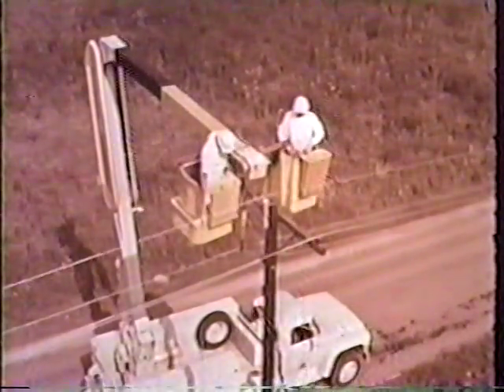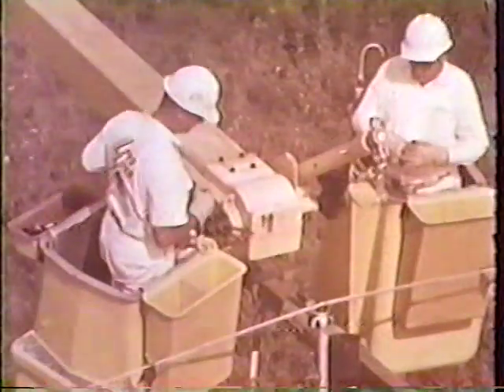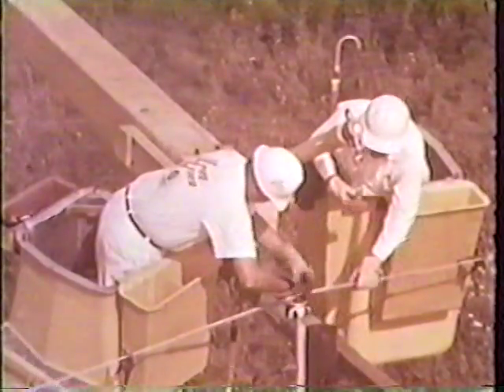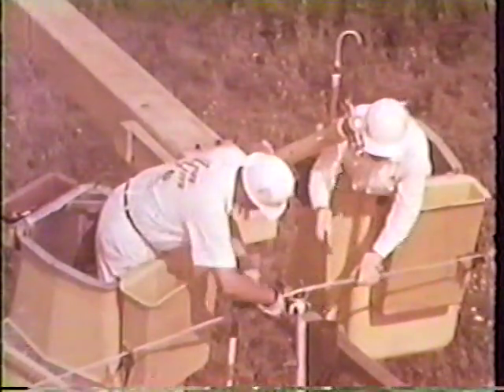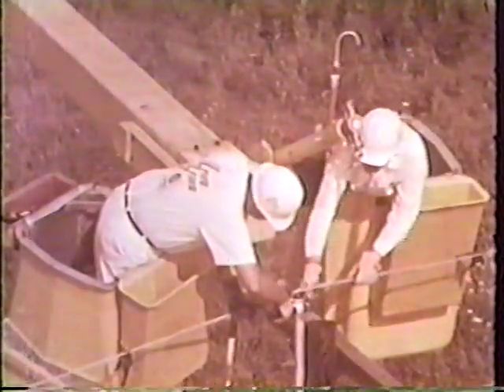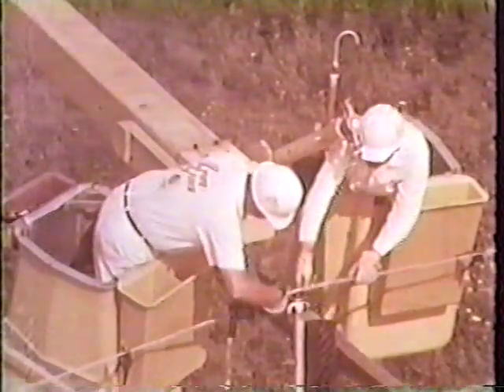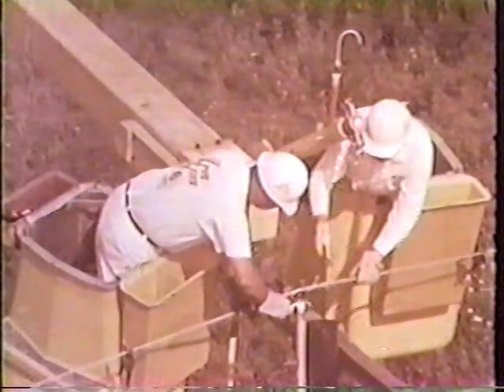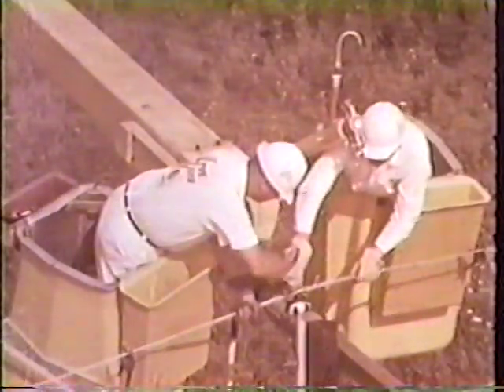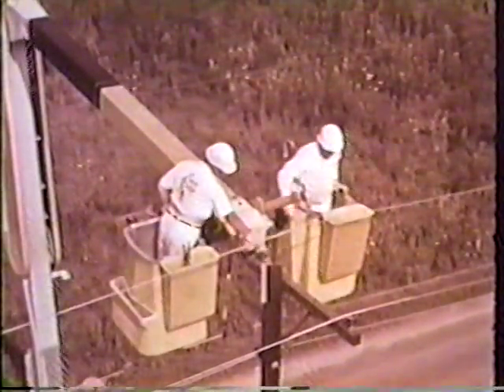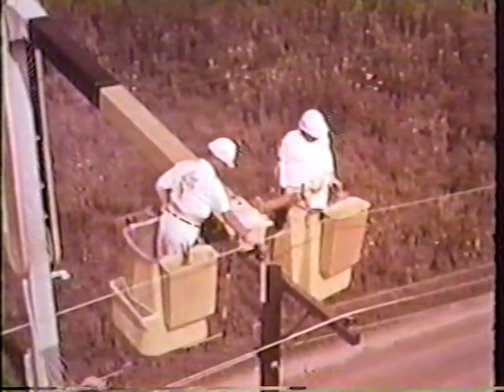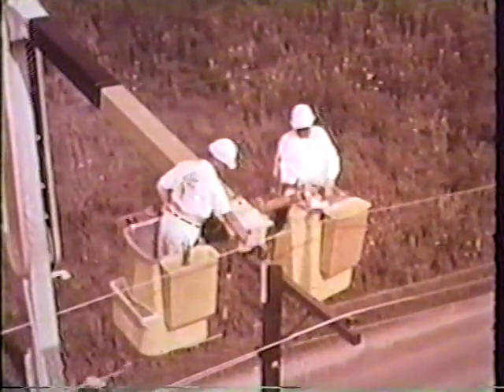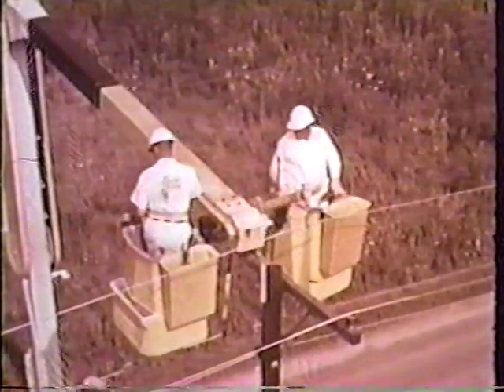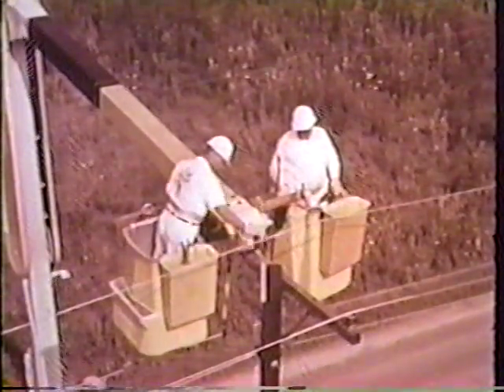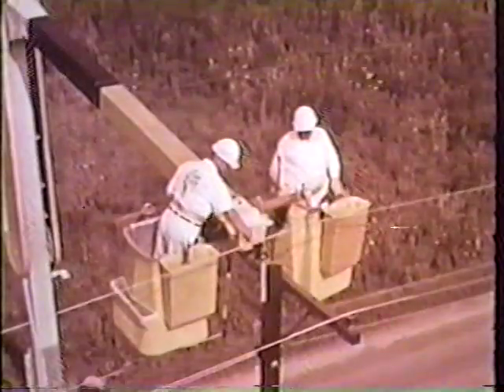Notice that both men always attach a bonding lead to the conductor before touching it. If either man should touch this 12.5 kV conductor before any bond was attached, he would feel a harmless but annoying charging current shock. After the tie wire is cut, the conductor is lifted into the pivot boom hook. Bonding leads are removed. The broken insulator is removed from the ridge pin, and the new insulator is threaded on the pin.